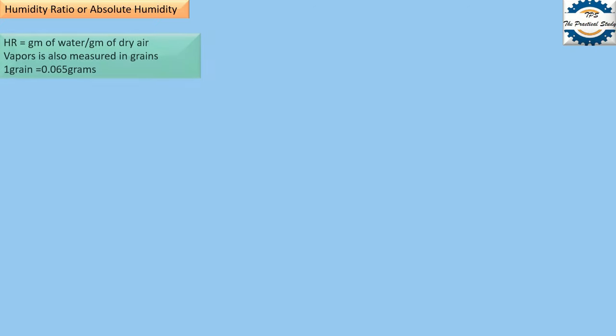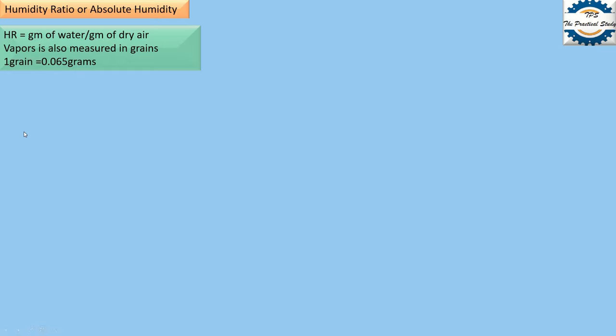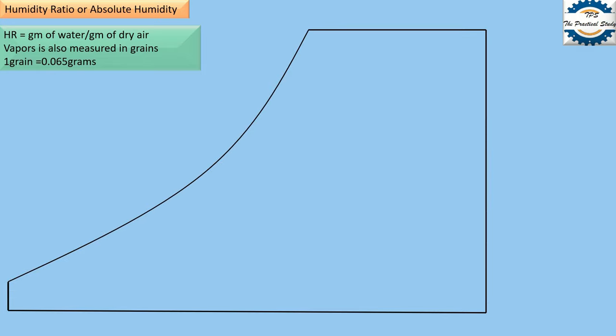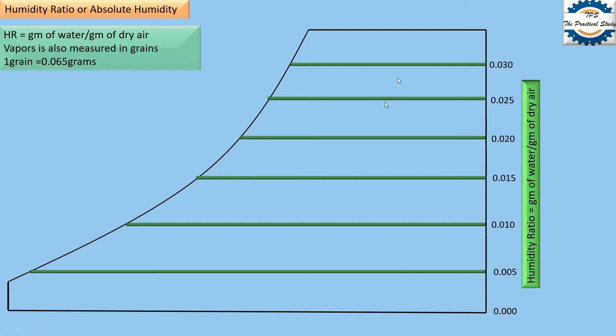Next is humidity ratio or absolute humidity. If you have 1 gram of air, the amount of water present in that 1 gram of air in grams is the humidity ratio. Since the water vapor quantity is very small, it is also measured in grains, which is the smallest unit — 1 grain equals 0.065 grams. The humidity ratio scale is on the y-axis (vertical axis), and its lines are horizontal lines extending toward the wet bulb temperature line.